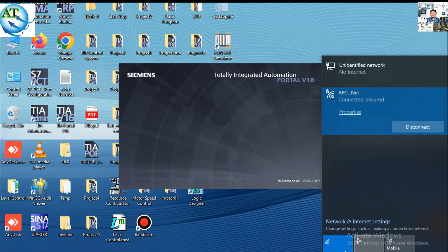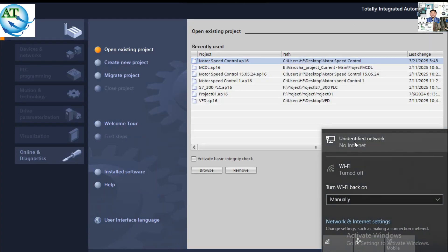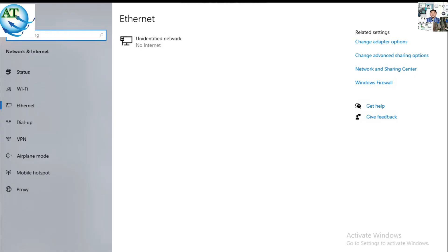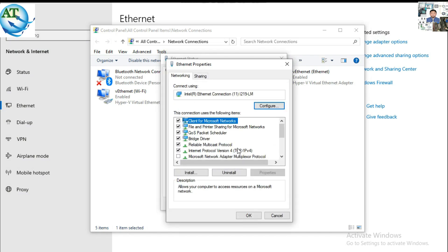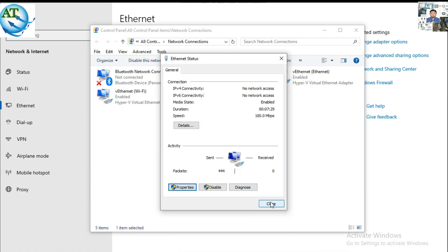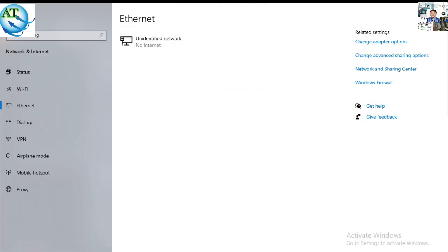On the PC side, we check the industrial Ethernet IP address to confirm it is in the same series as the HMI. We go to Network, then Change Adapter Options, then Properties, then IPv4. Here you can see the IP address is in the same series as the HMI. The right side shows the HMI IP address and here the PC IP address — both are the same series, so there is no problem and they can communicate.